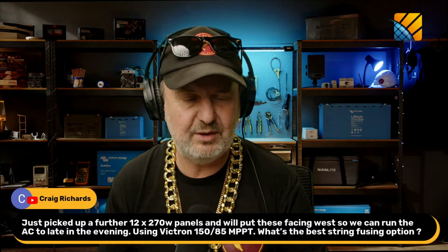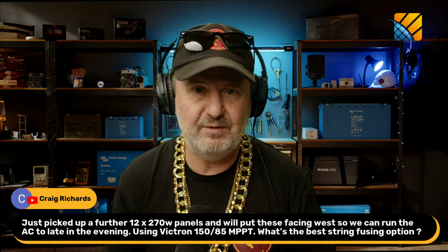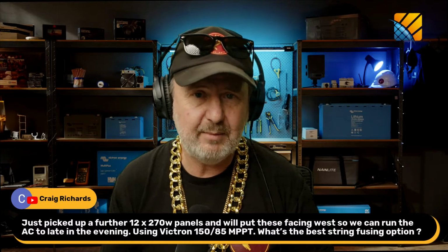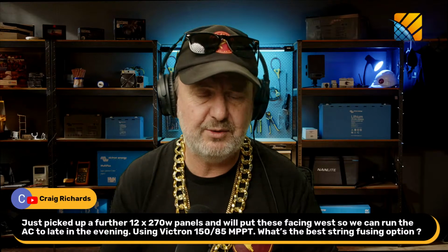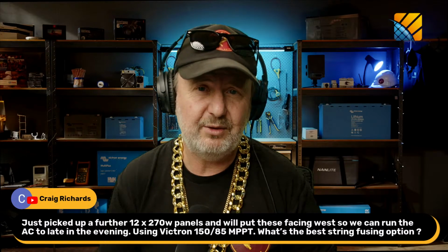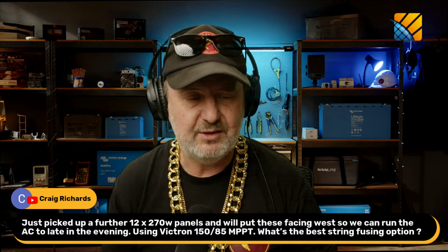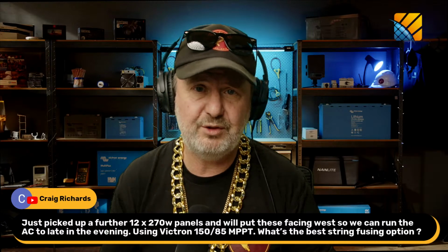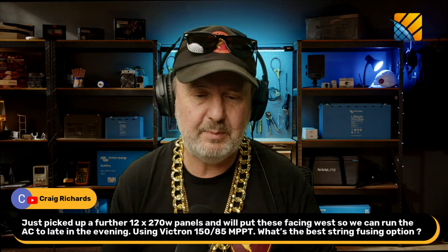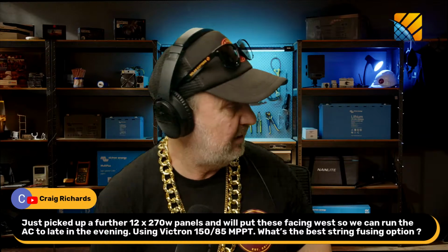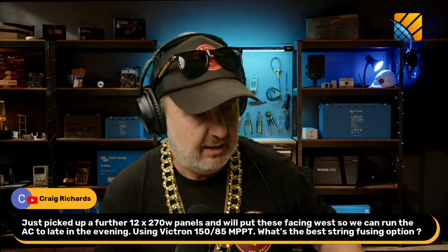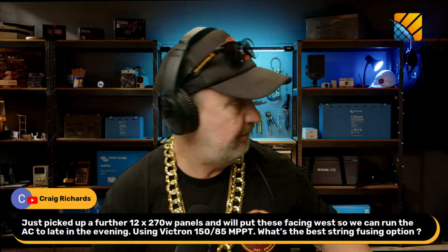So I'm guessing with those 270 watt panels, probably strings of 3 would be okay. Most of your 60 cell modules will top out about 40 volts, so 3 of those is 120 volts. So strings of 3 means you've got 4 strings. Now this is where it gets a bit complicated, and I probably would need to - actually I've got a drawing. Hold on a sec.